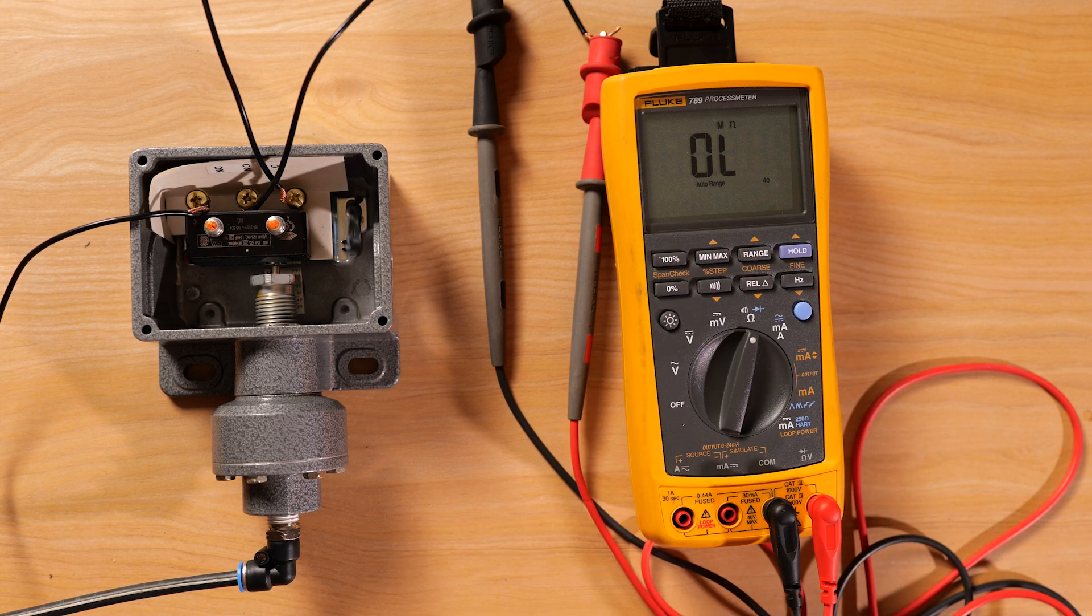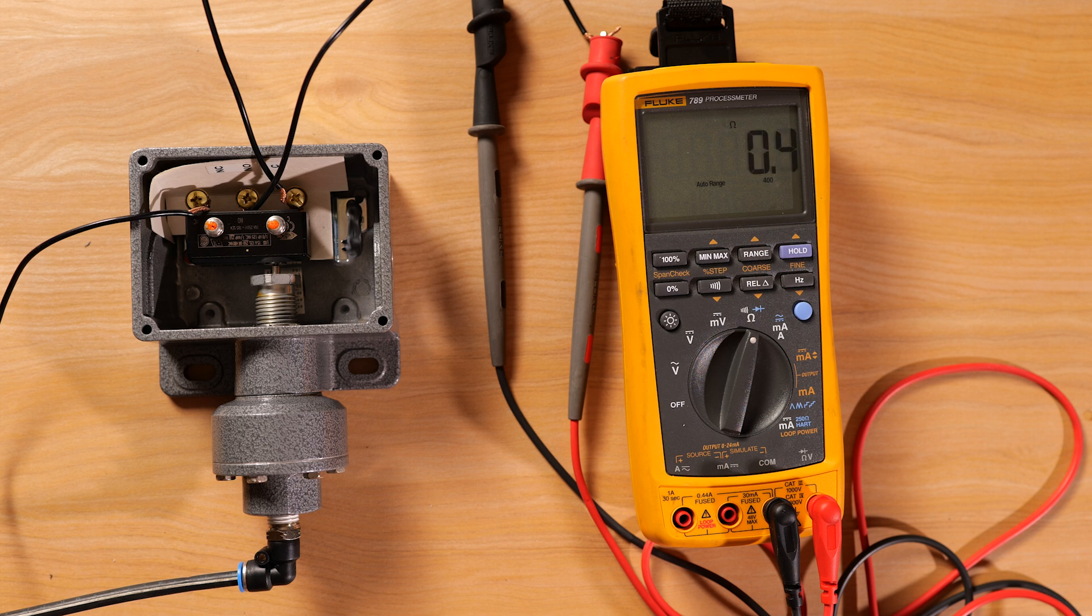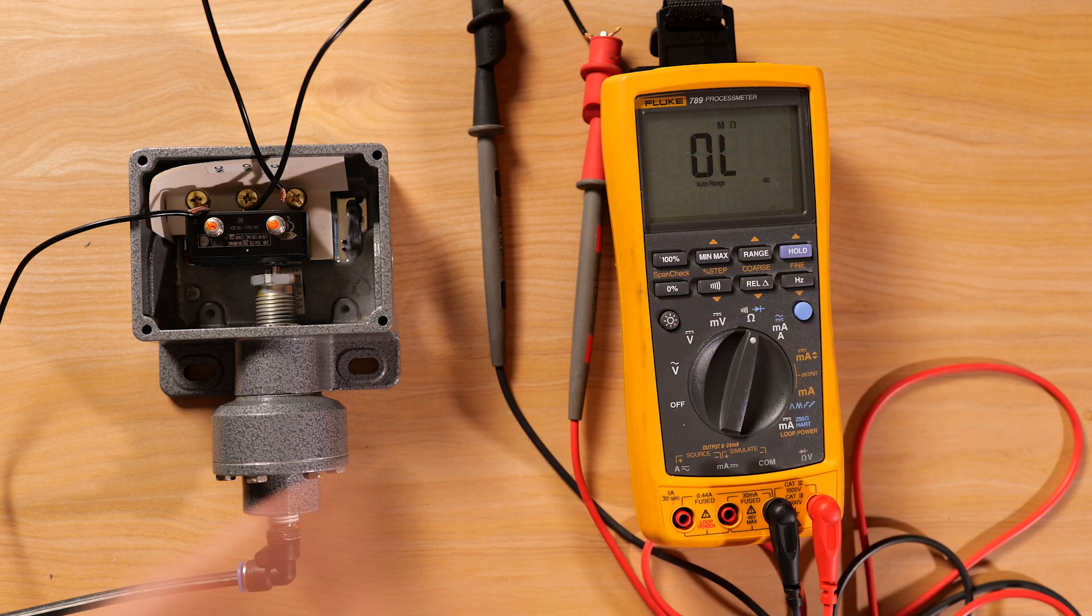So right now we're showing OL, no continuity, but whenever we have pressure applied, we're seeing that reading, ohm reading, turn on and turn off, right? So close and then open.